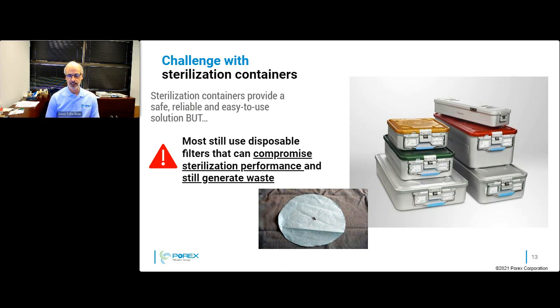Not only that, but it does have to be manually taken care of. So once these containers are done with their use for the application, they have to go back into some kind of facility or maintenance facility where they would replace these filters one at a time. So again, the key is that your weakest link is still here, your filter, because these filters will still have a bacterial filtration efficiency of that filter paper. So even though these containers are excellent for storing sterile devices and are easy to stack and very versatile, if you do use an inferior filter, you still have a risk of having bacteria enter that device through the filter media itself.